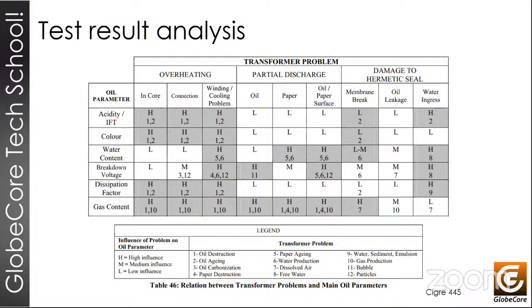So if we see that we have a high acidity and we see that overheating has a strong effect on the core, it will lead to the destruction of the oil and aging of the oil. Now, what the letters H, L, and M stand for is the impact that these issues have. For example, we see that oil leakage has little effect on acidity, while overheating has a strong effect on acidity and interfacial tension. And the strong effect explains to us that oil breakdown and aging can and will occur. Now, for example, partial discharges will have a moderate effect on the breakdown voltage, but high effect on paper.